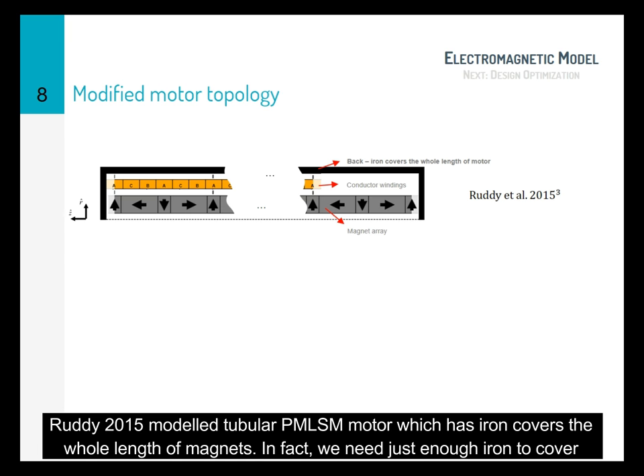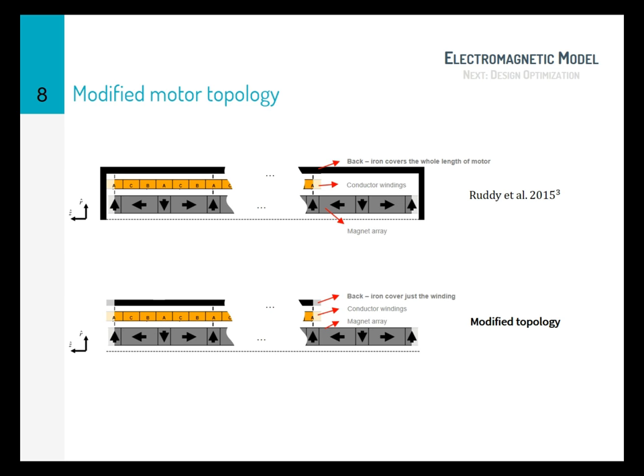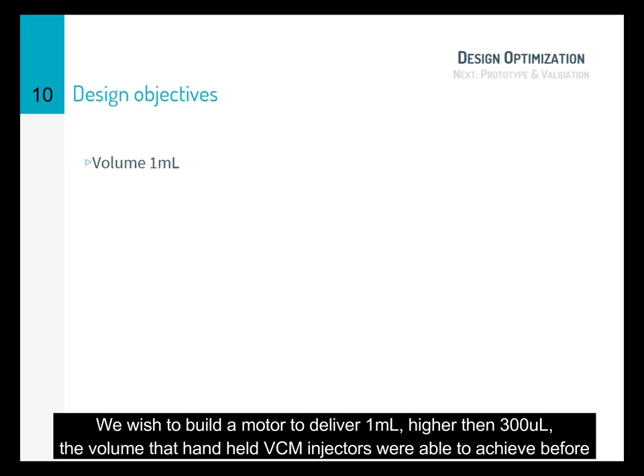Ruddy 2015 modeled a tubular permanent magnet linear synchronous motor which has iron covering the whole length of the magnet. But in fact, we need just enough iron to cover the coil. The trade-off here is that there will be cogging force. We wish to build a motor to deliver 1 milliliter of drug volume, which is higher than the 300 microliters that voice coil motor injectors were able to achieve in previous works.